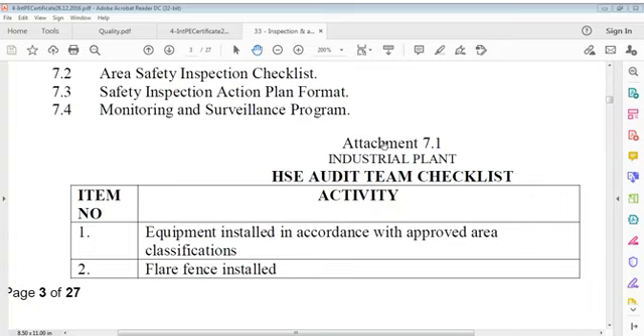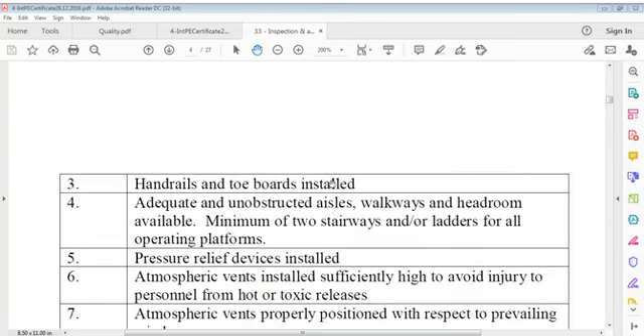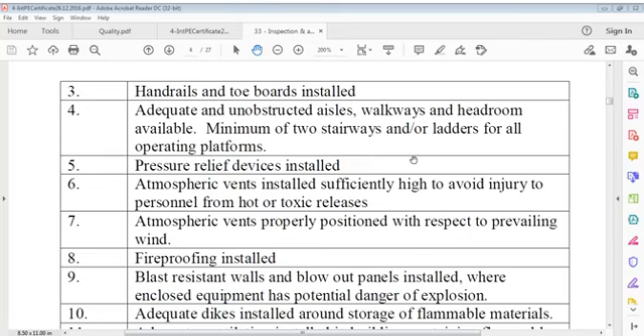This is an example I'm taking from a certain source: equipment must be installed there when you are going to do audit, in operation standard, not in project standard. In the oil industry, energy industry, whatever you call it, equipment is installed in accordance with approved area classification. There may be a flare fence installed because of flare. There can be handrails and toe boards installed. Adequate and unobstructed egress, walkways and headrooms available, minimum 2 stairways or ladders for all operations platforms.